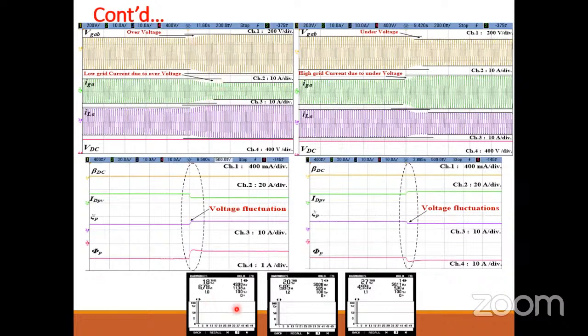So if you go to the harmonics, you will realize that in the normal condition it is 2%, but during the over voltage conditions the grid current decreased, which means your harmonics will increase. So the grid current magnitude decreases. Normally this was 5.8, but this time it is 4.9. So the grid current magnitude decreases, harmonics increase. At the same time, here the grid current increases because of the under voltage conditions. So you will see here the current magnitude has increased, and this component has decreased because of the harmonics THD calculation.